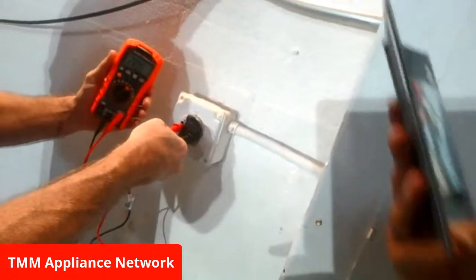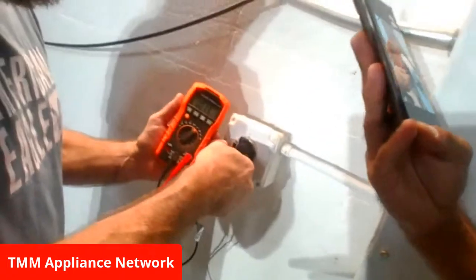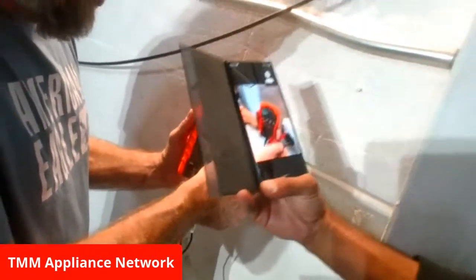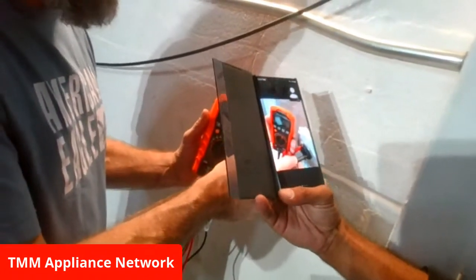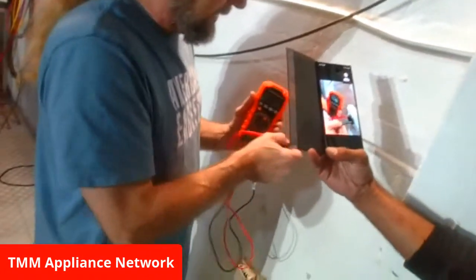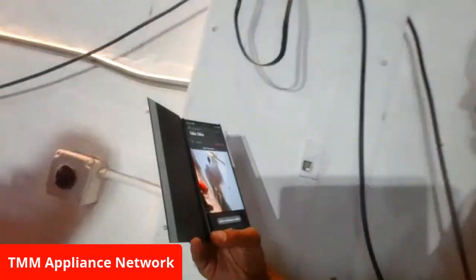To check the outlet over here, we want to check the two prongs first, and I am getting a reading. Let me show the reading. If your meter leads don't give you a reading, move the leads in the outlet left or right to see if you get a reading. If not, if your meter leads are a lot shorter than this one...